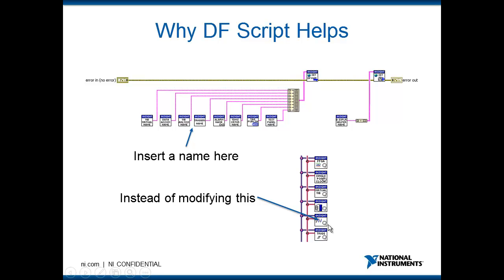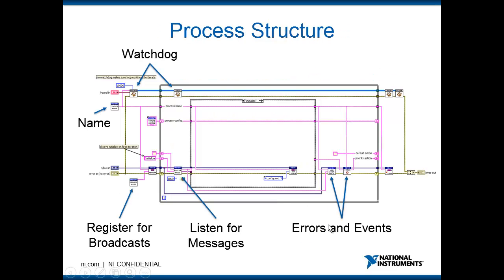So one thing that you have at your disposal that can help with this is that anytime you need to add a new process to the source code, you can start with our template. Now I'll open this VI up in a moment, but the SDK does provide a process template for custom devices that use the same queued message handling API, that has the same initialization and shutdown strategies. It handles errors in the same way, and it uses watchdogs in the same way as our regular InsightCM processes. So this allows you to insert new processes that the controller knows how to interact with and that can talk on the data flow script. So let's go ahead and I'll show you where that's at right now.